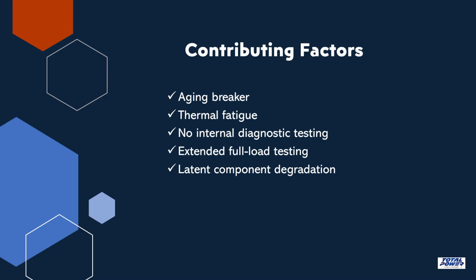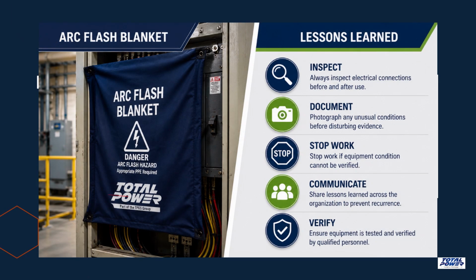Finally, let's look at what prevented this from becoming a serious injury. Although equipment damage occurred, several positive controls prevented this event from becoming a serious injury. The arc flash blanket contained the arc flash inside the breaker enclosure. The technicians immediately recognized abnormal operating conditions. They removed the electrical load without hesitation. The generator was shut down quickly. The area was secured. The incident was reported.